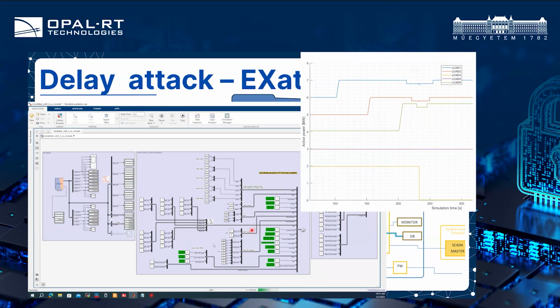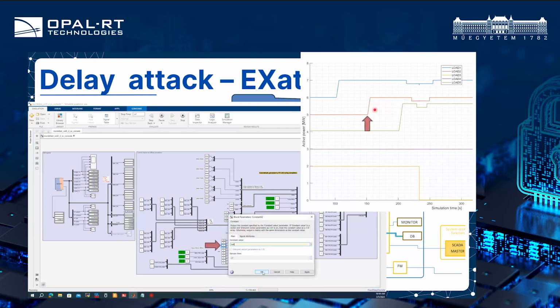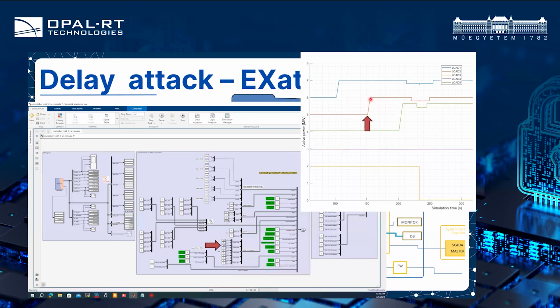Now we're going to add another mismatch, another failure in the system to load 2, adding another 1 megawatt of load. Here you can see another 1 megawatt step in load 2, and again the numbers are changing. The control algorithm tries to balance everything, and up to this point it successfully does so, only needing to use new set points for the generators and nothing else.